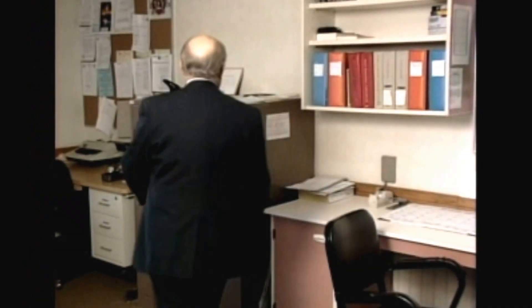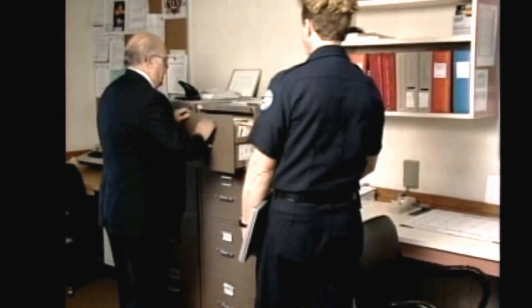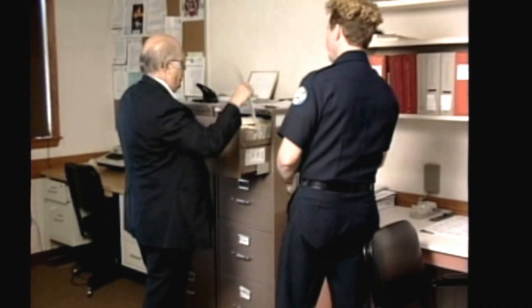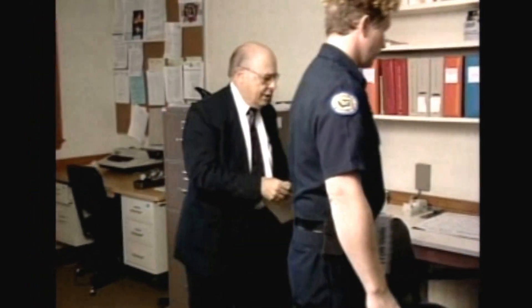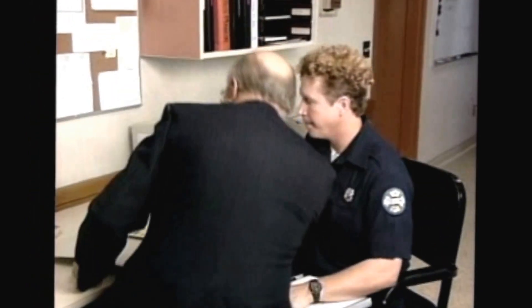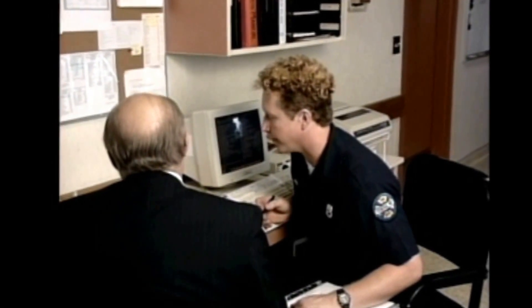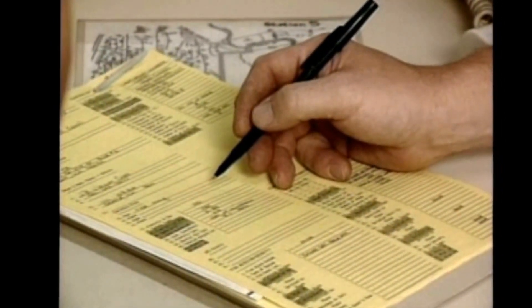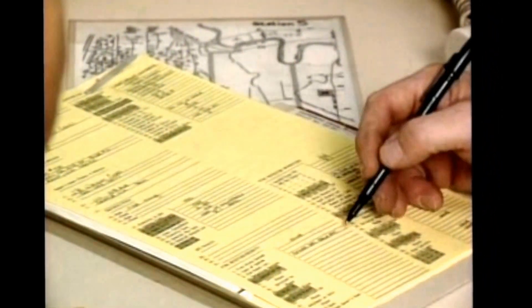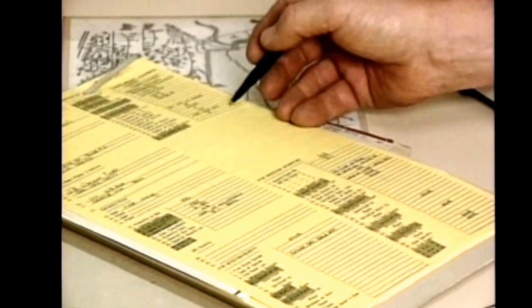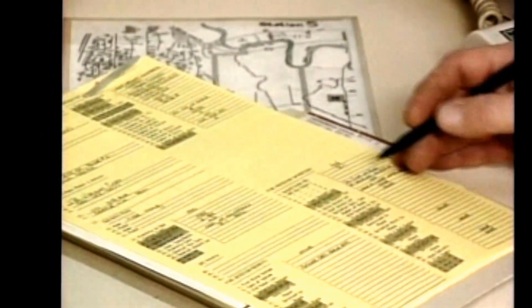Fire extinguisher maintenance is the responsibility of the property owner. Fire extinguishers should be thoroughly inspected at least once a year. Some types of extinguishers will require a thorough examination by a manufacturer's representative at regular intervals. Owners should keep records of maintenance and inspections, and fire service inspectors should review these records during their visit.